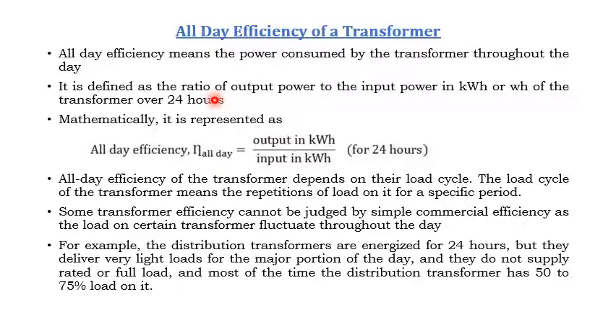All day efficiency of a transformer. All day efficiency means the power consumed by the transformer throughout the day. It is defined as the ratio of output power to input power, in kilowatt hour or watt hour, of the transformer over 24 hours. So that means overall per day.